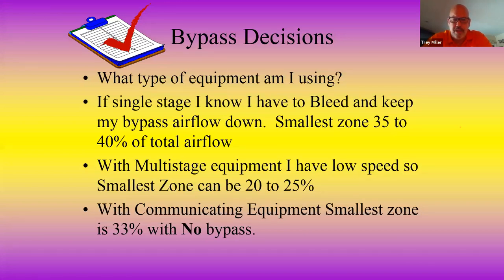Now, what's kind of funny is we go to communicating systems, which is the newest craze, and they tout no bypass. But without a bypass, our smallest zone is 33%. We're almost right where we were with the single stage piece of equipment. The problem is, if you don't have a bypass, the system can't drop the fan speed below 33%. Therefore, we've got problems if our smallest zone is smaller. Then we're going to have to use a bypass, or we're going to over-condition the areas, or over-condition the zones. And in some of these communicating systems, you have no control over it. It does what it wants. Some of them you can wait.